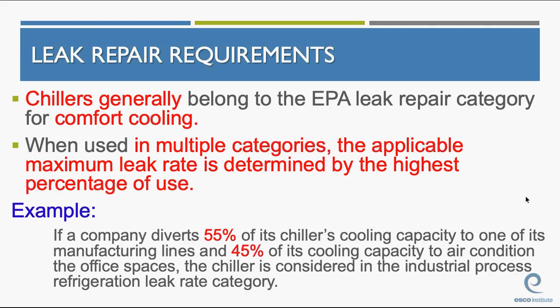Chillers generally belong to the EPA leak repair category for comfort cooling. However, if used in multiple categories, the applicable leak rate is by the highest percentage of use. And there's an example here. If a company uses 55% of its chiller capacity in one of its manufacturing lines and 45% of it in the air conditioning of the office space, the chiller is considered the industrial leak rate category. If it would be the other way around, it would be considered comfort cooling. Highest percentage of what it's doing.